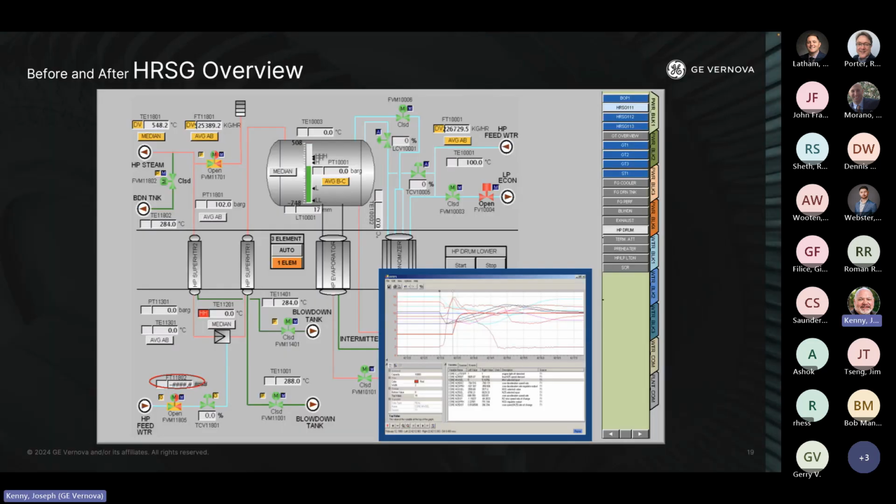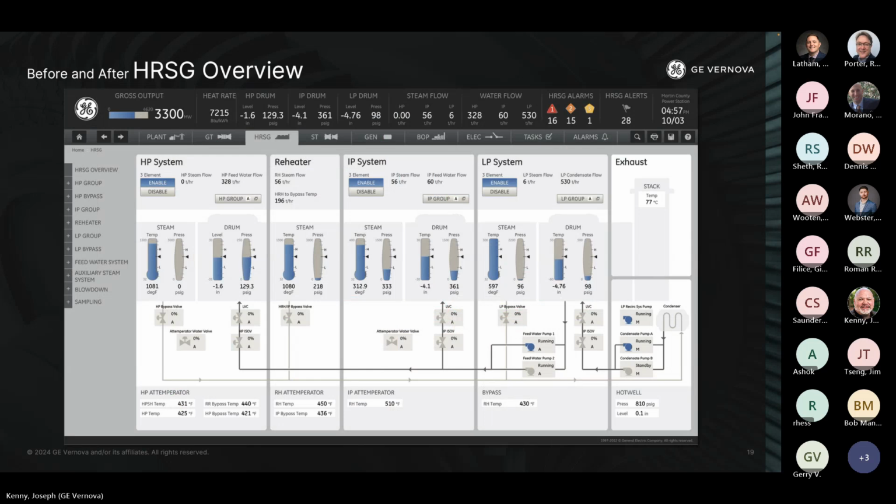So just to show you very quickly, just some of the quick conversion outlines. This was actually a gas turbine interface that was done years ago. Applying these principles to it changed it from this to this. Now, it's not necessarily less complex. It doesn't have less things in the screen, but it is a lot more scannable and a lot more organized because of the principles that we were talking about, like alignment and scale.